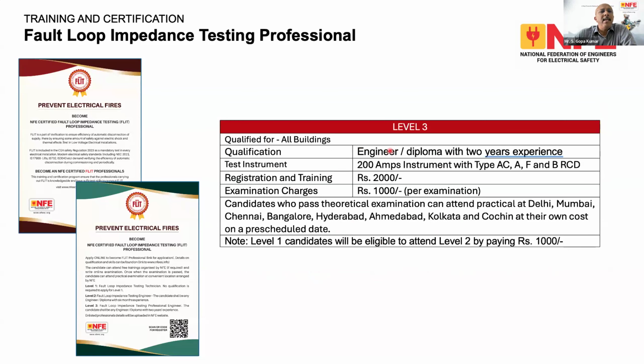The last one is level three FLIT professional. They will be qualified for doing tests in all kinds of buildings. The qualification required is engineers or diploma holders with 2 years experience. They have to have a 200 amps test instrument, and the instrument should also have the facility to test type AC, A, F, and B RCDs. Please note that even though the name is written as fault loop impedance testing professional, the actual job is not only the fault loop impedance test, but here in level 3, we are covering a lot of additional safety measures. Almost all fault protective measures are included in level 3.